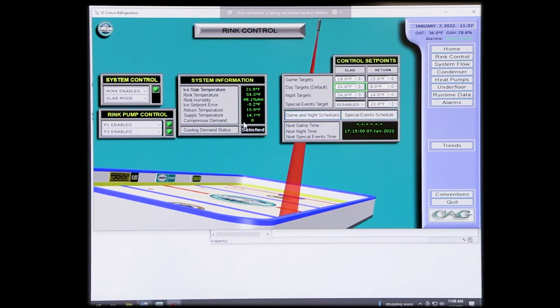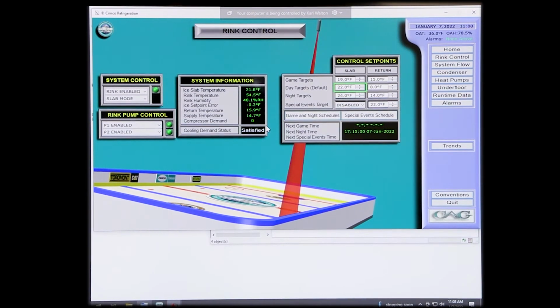Okay. Compressor demand, based on the algorithm within the program, you'll see 1, 2, or 3 here once it calls for cooling. Okay? And as it starts to pull the temperatures down, which you'll see in the trend logs, it'll start cycling them back the closer we get to that temperature setting. That algorithm is based on a 10-degree max differential temperature. Okay? That 10 degrees looks at the return temperature and the supply target. Okay? So, sorry, slab target. So if we're looking at 22 degrees, my max DT is 10. So it's going to look for this return to get down to around 12. Then it's going to start cycling compressors back.